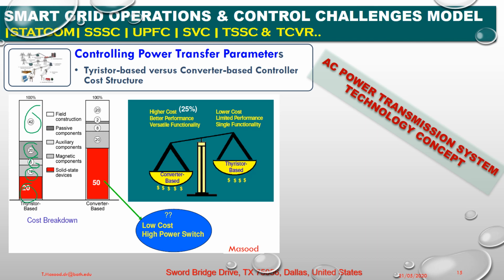If you come to the other side, the converter based, the major cost is the solid state devices, and 20% is magnetic components, auxiliary components 8%, passive components 2%, and 20% field construction. So now the overall cost factor: the SVC demonstrates low cost, limited performance and a single functionality, and STATCOM will demonstrate a higher cost, better performance and versatile functionality. The STATCOM is 20 to 25% more expensive compared to the SVC. So, high cost, but better performance and versatile functionality. We would definitely prefer 25% more cost but better performance and versatile functionality.